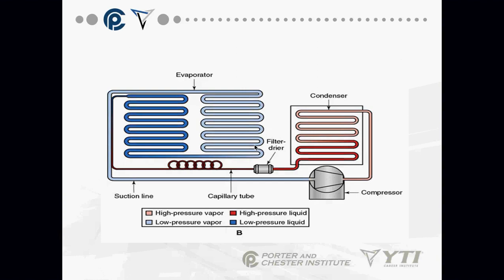Okay, now, here's the key. By the way, in our shops, you're not going to see us replace the filter dryer every single time we open the systems. The reality is we open the systems like 20 or 30 times a term, and we don't replace the filter dryer every time. We put a good vacuum on the system, and we probably replace them twice a year.